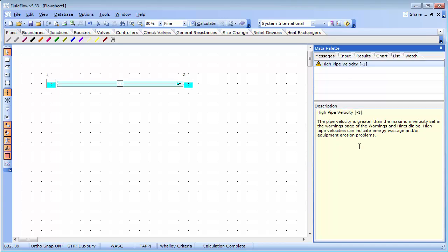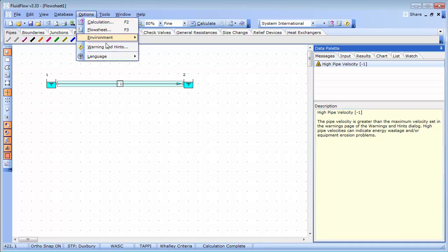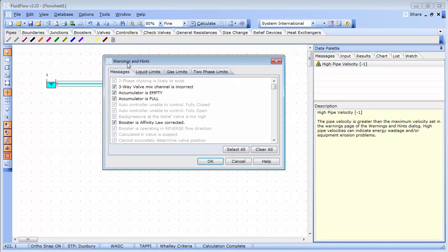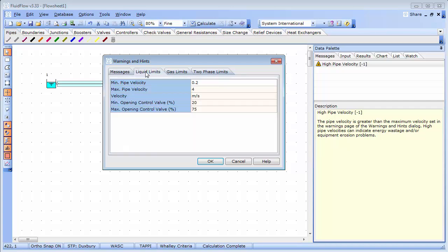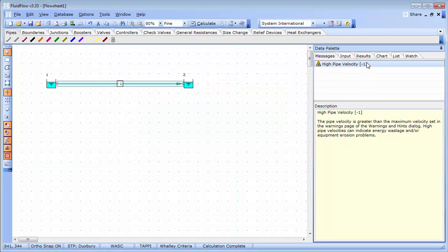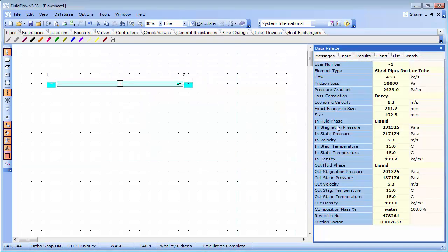This description notes that the velocity is higher than that set as a maximum limit in warnings and hints. And this is where we set the main design limits for our model. To access these settings, select options and warnings and hints. And in this case, we are looking at a liquid system. So, we can see the maximum pipe velocity is set to 4 meters per second. And since our pipeline flowing velocity is 5.3 meters per second, we have a warning.